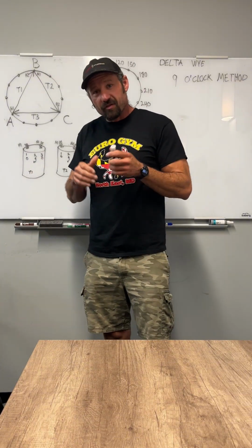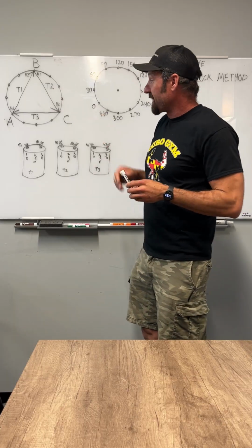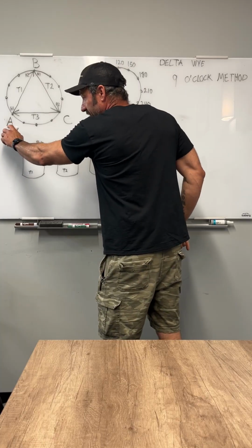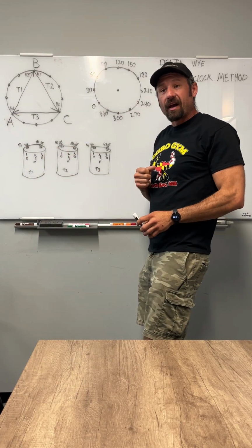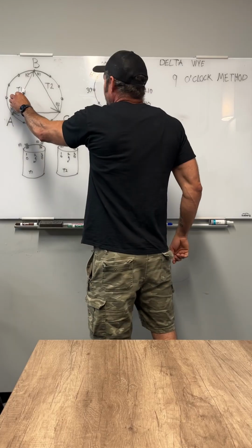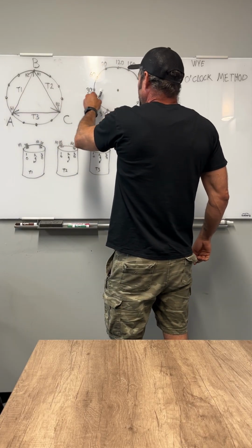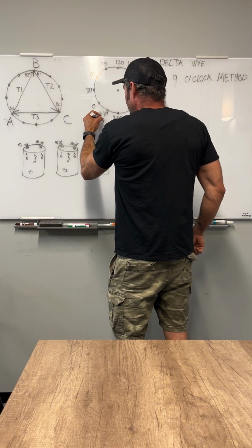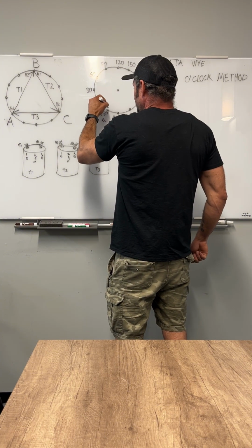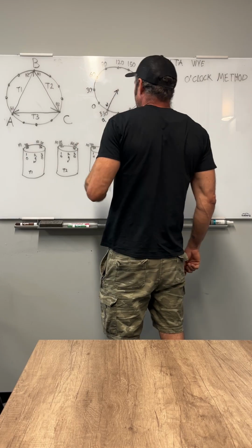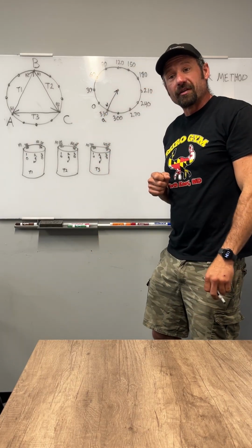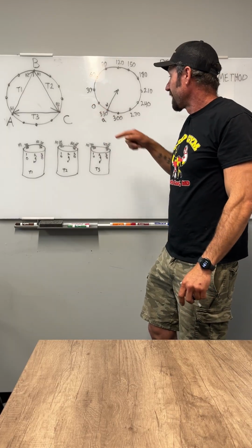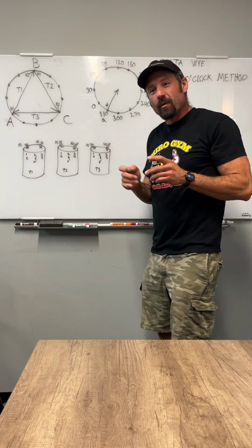Now, generally speaking, if we're looking at this vector and I want to use the X1s, I'm going to reference my A phase starting at the tail of this vector. And I would take it and I would slide it over, and it would slide right here, which would end up being A phase, X1, and that would be at 330 degrees, or 30 degrees from 0. Now, there's another way we can do this.